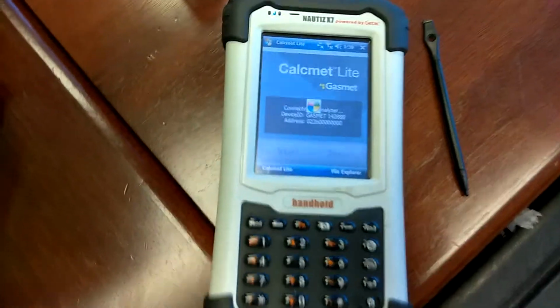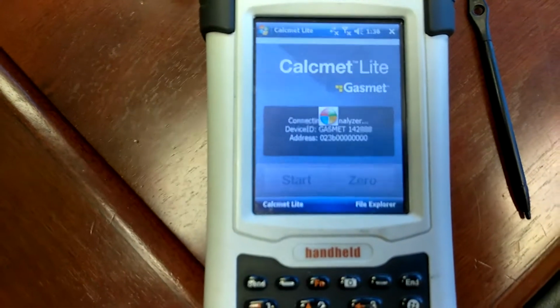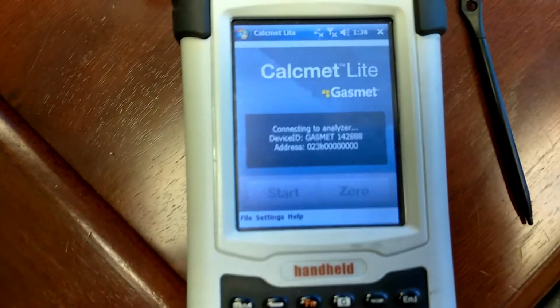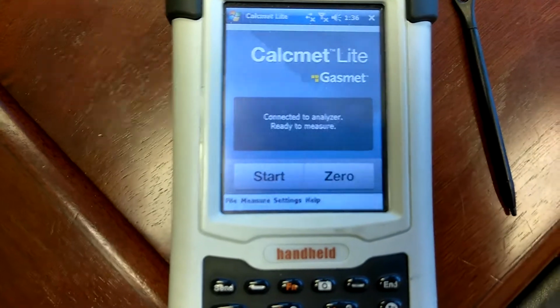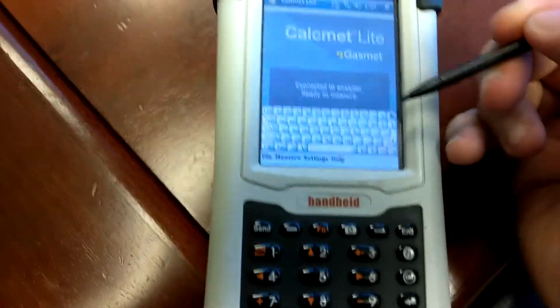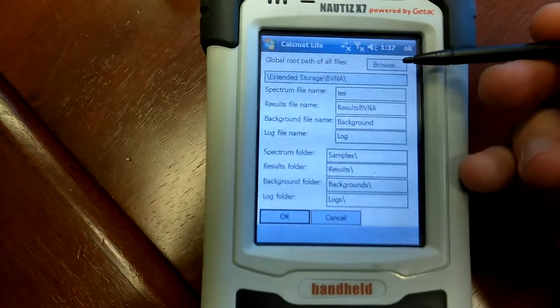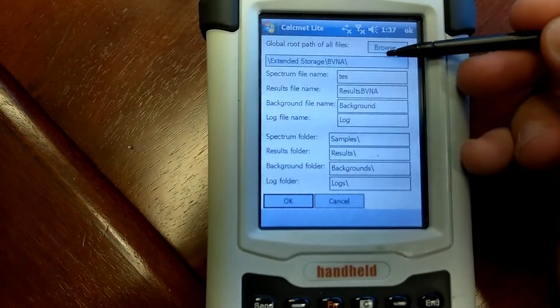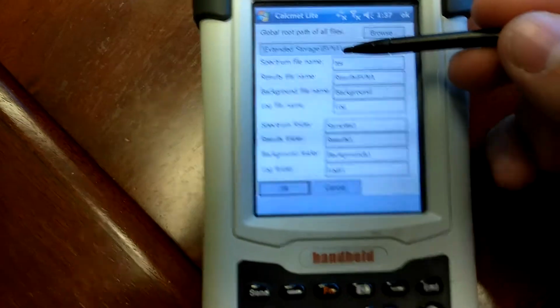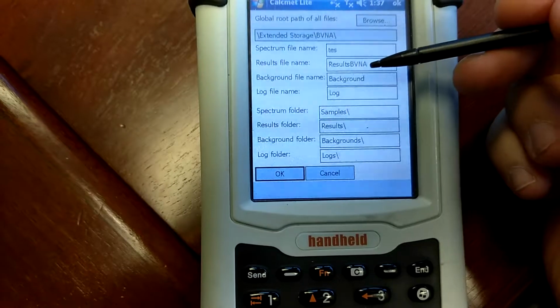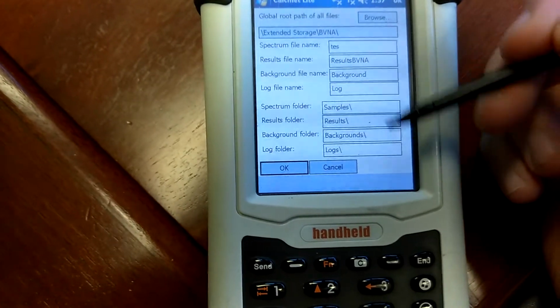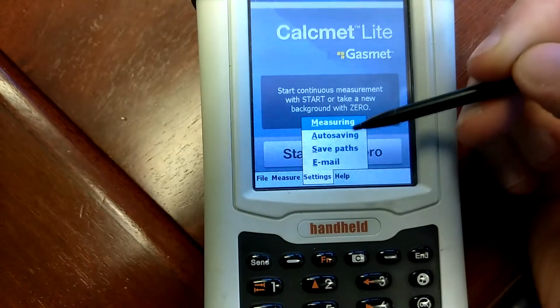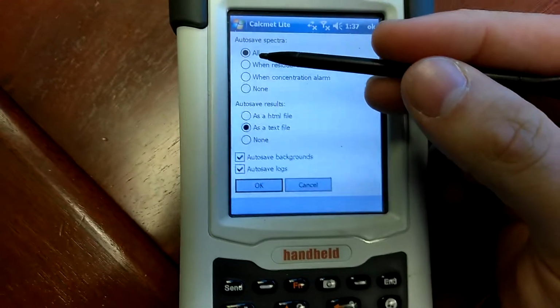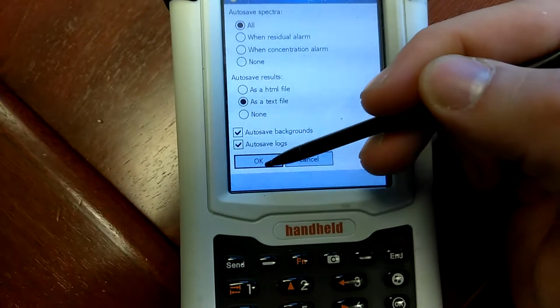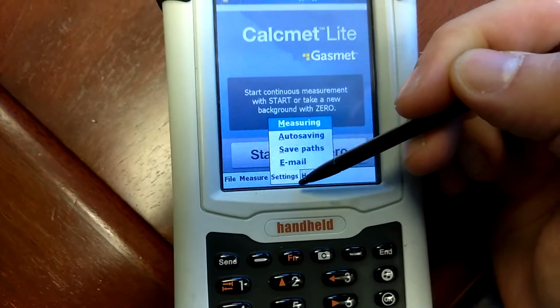CalcMet will now spend a few minutes detecting the analyzer. They'll connect via Bluetooth. It only takes a couple of seconds. Our very next step is going to be to check a couple of things to make sure that we're ready to go. We'll go over to settings and then save paths. I showed you how to set this in a previous video, but you'll want to make sure that you browse yourself into an external storage and then an intelligible name so that you can find your results. So you'll set the browse and then this results file name. If that's okay, make sure you're on auto-saving. All, as text file is fine, but you want to make sure you save that. If you don't, otherwise you might not save everything.